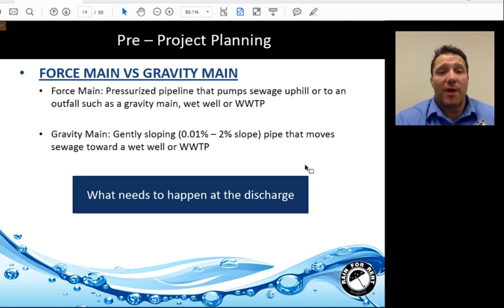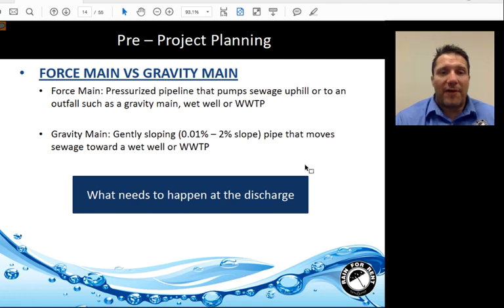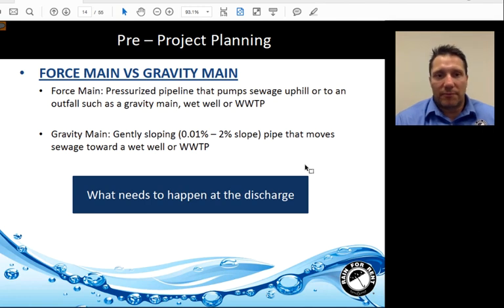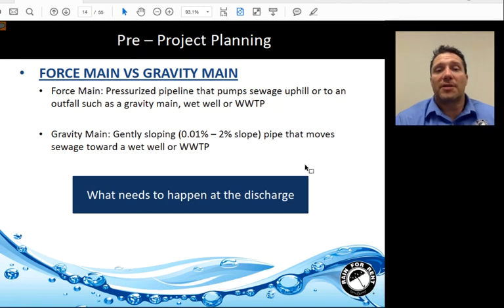Force mains versus gravity mains: A force main is a pressurized pipeline — for example, when you have to pump sewage up a hill or lift it from a lift station into a pressurized line. A gravity main is a gently sloping pipeline that moves sewage downhill. A force main is under pressure; a gravity main is open to the atmosphere and functions due to gravity. It's important to know which type we're discharging into, as it determines whether we need to overcome pressure at the end of the discharge.